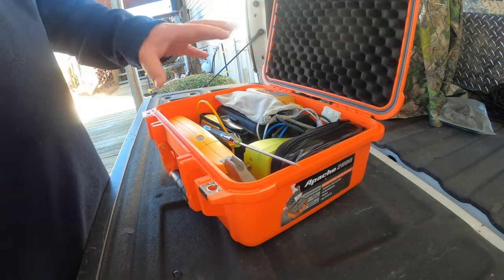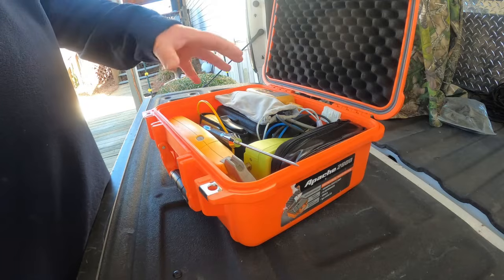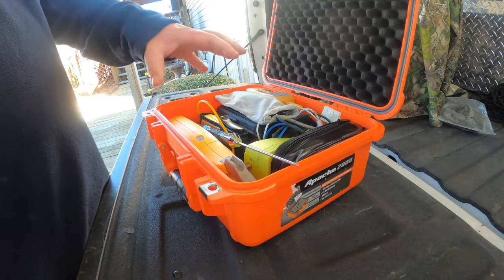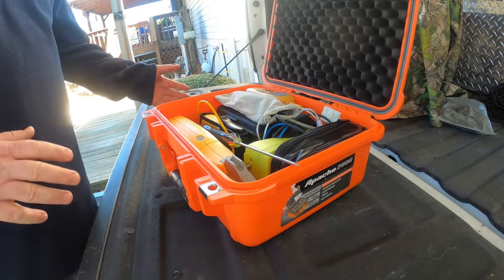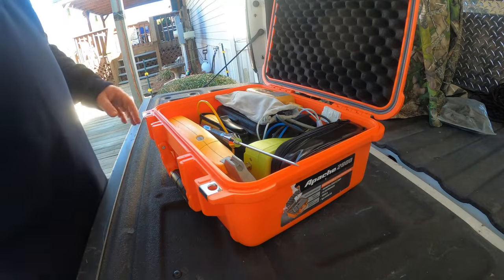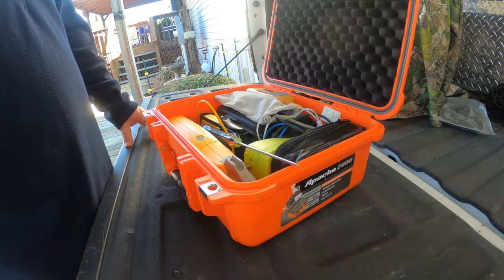Like I said, if it's shaking, you've got your high voltage, you're getting your low voltage. If you're sitting in there rocking, then you've got a bad motor. You need to replace the motor, you need to replace the module. Depends on whether it's warranty or not warranty. It's kind of how I handle that.